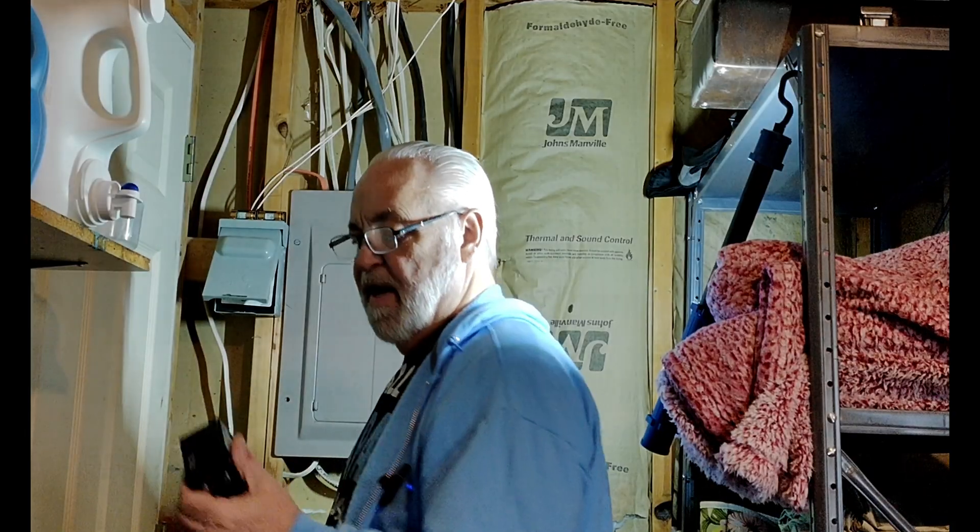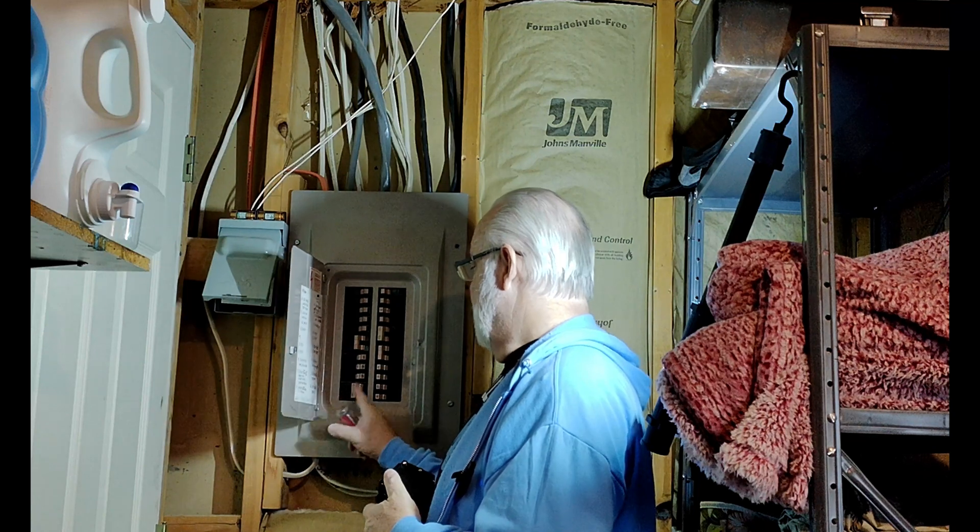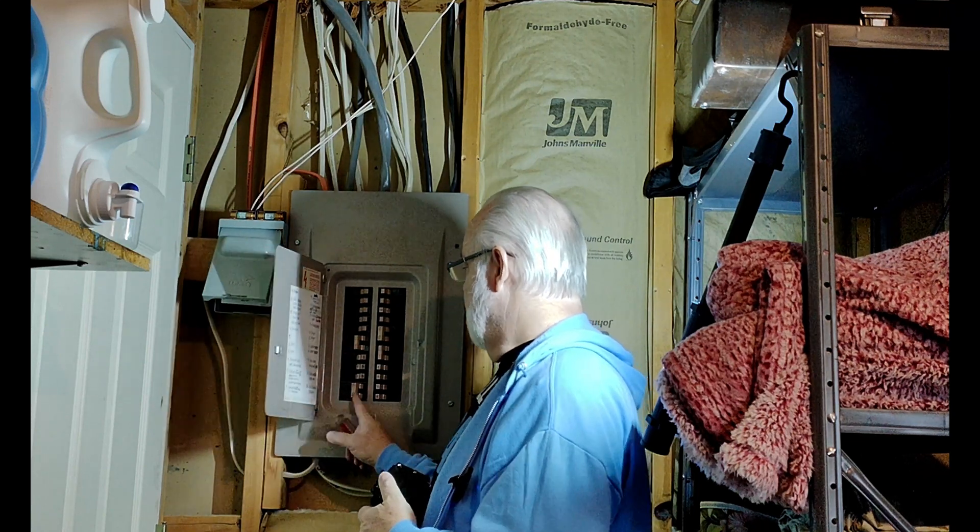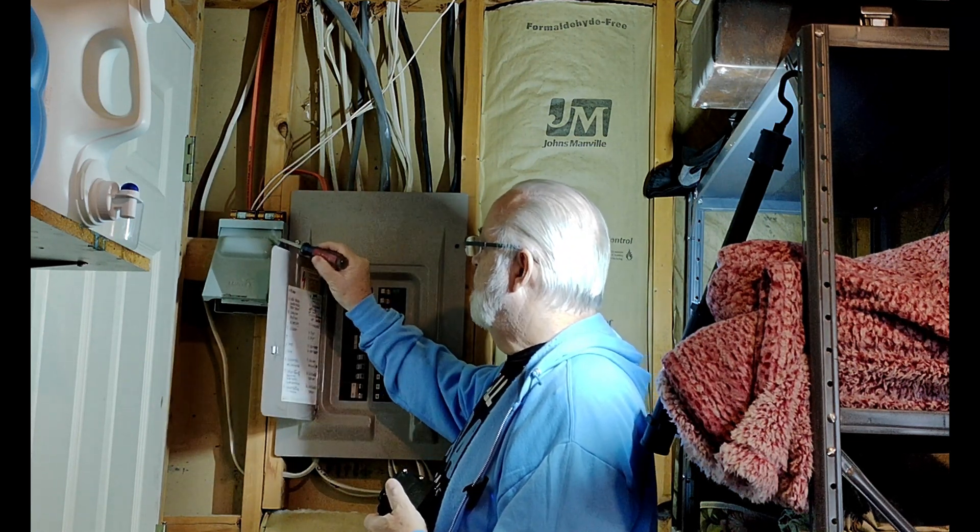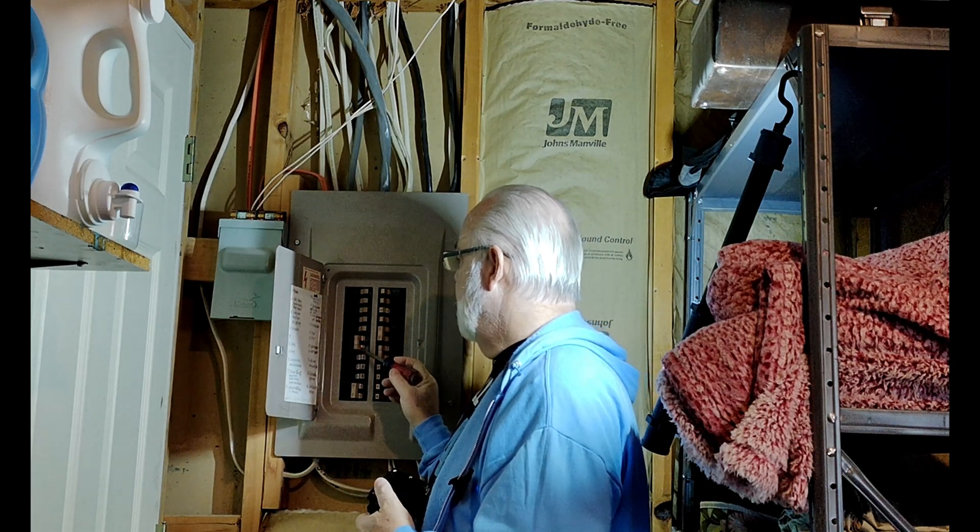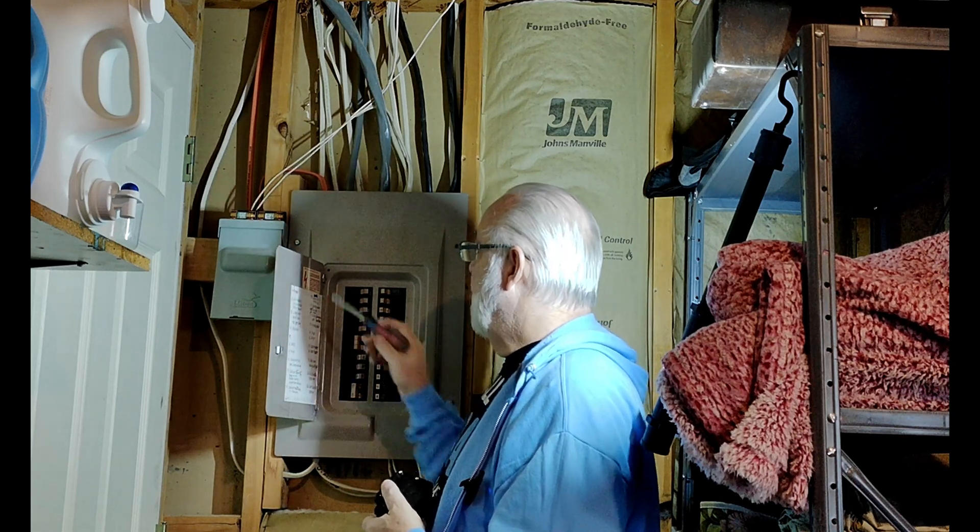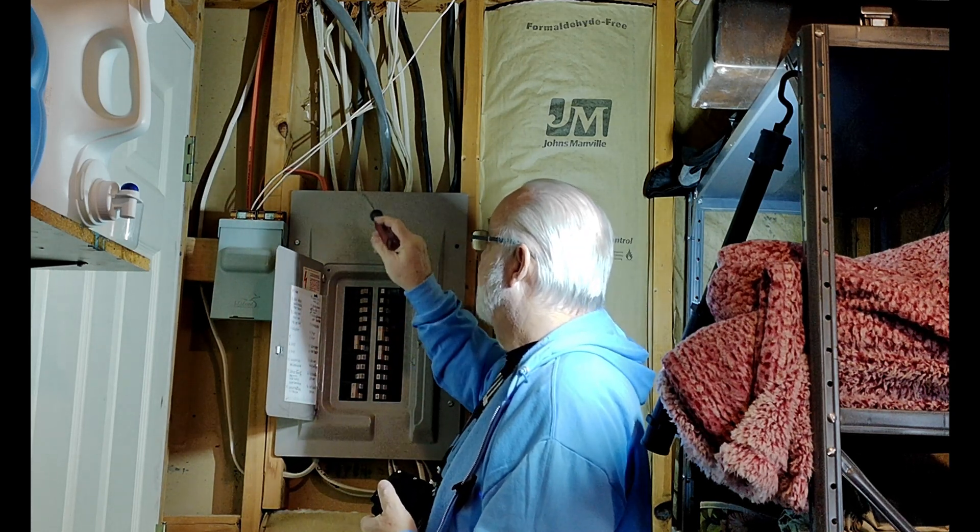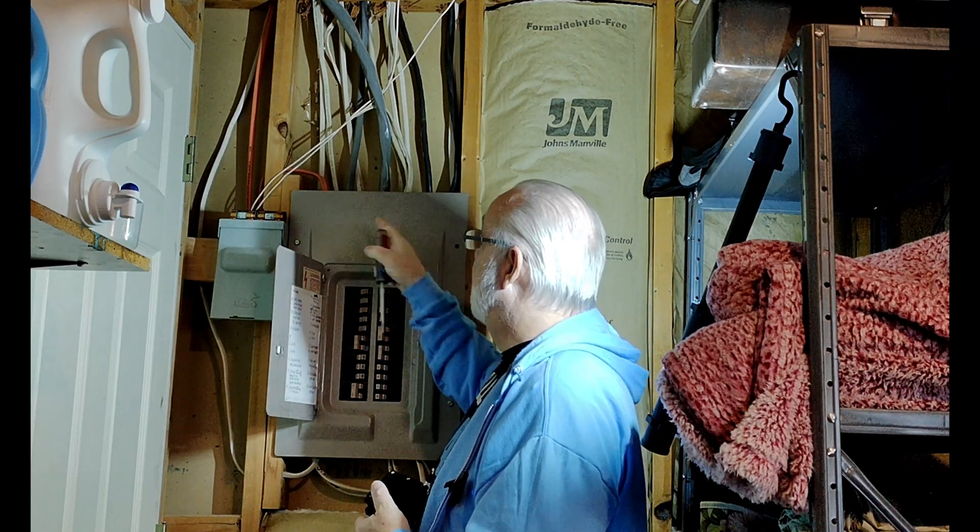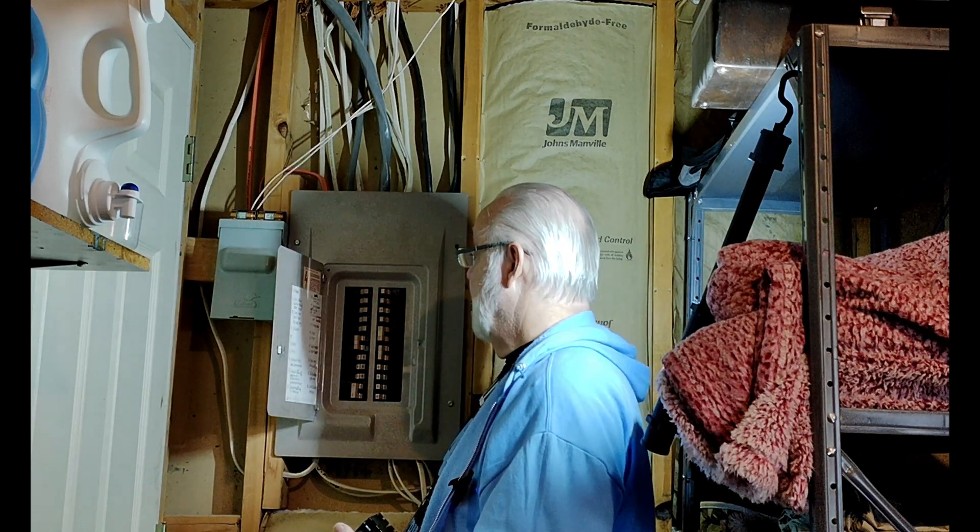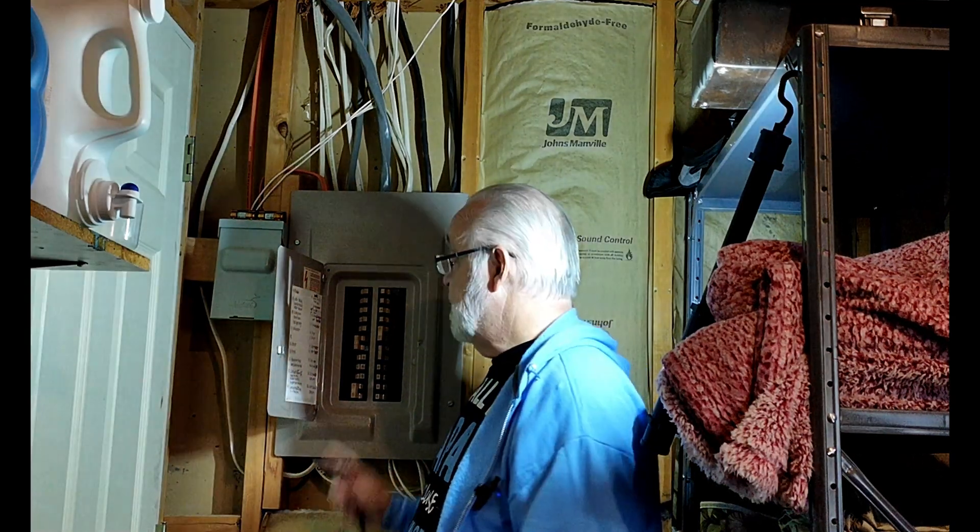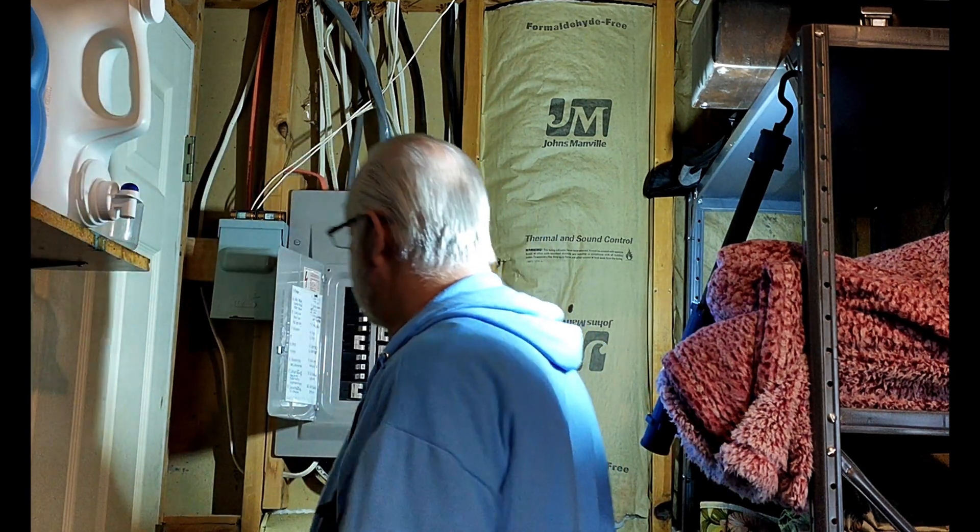So we've got our 60 amp breaker that's going to replace the 50 amp right here for the garage. And then we're going to rewire the AC unit to this breaker. Right now they've got it actually wired into the two hots coming from outside—directly into the hots, which is completely insane. You'll see here in a minute. I don't know how they got away with it. The minute we took this cover off, it's going to be a heck of a surprise.